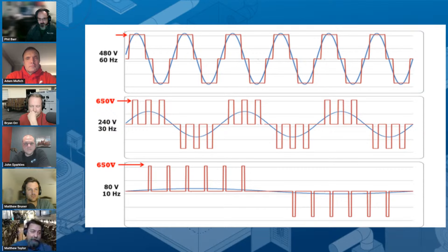That's a great explanation — I always heard you can use a VFD to make three-phase power but never applied it that way. So the computer knows the timing it needs to set for those other two phases and just programmatically creates them. Typically when we do that, we run the VFD at full speed at 60 hertz, but there's no reason we can't use it as a real VFD with a soft start and run at half speed at 30 hertz — it has that capability, we're just probably not using it for that in that particular application.